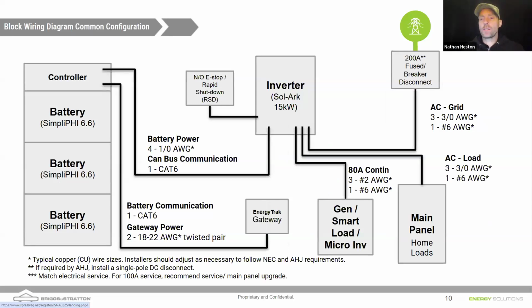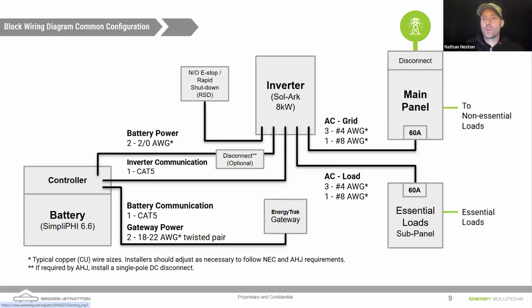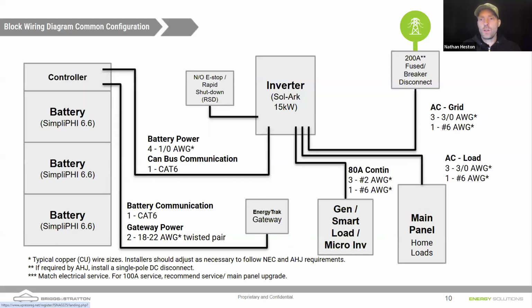Notice that the wiring is a little simpler here. I'll point out the difference between the loads. With a smaller inverter like a Sol-Ark 8K or 12K, unless you're off grid, some of your loads are going to be in your main panel, and you're only going to be able to back up some essential loads. We'll typically move over the important things, the internet connection, things like your refrigerator, things that you definitely want to have backed up in a grid outage situation.